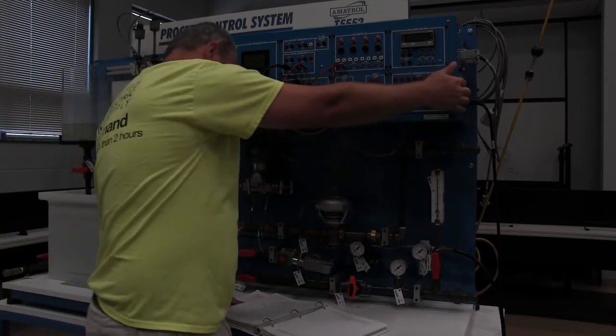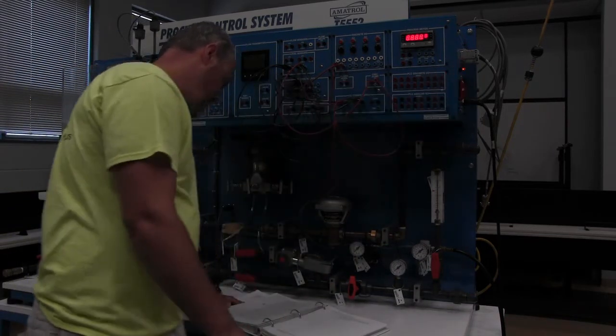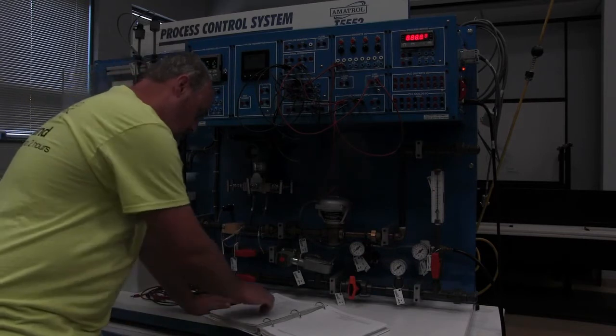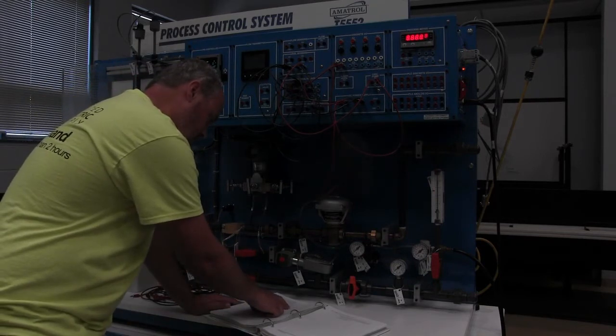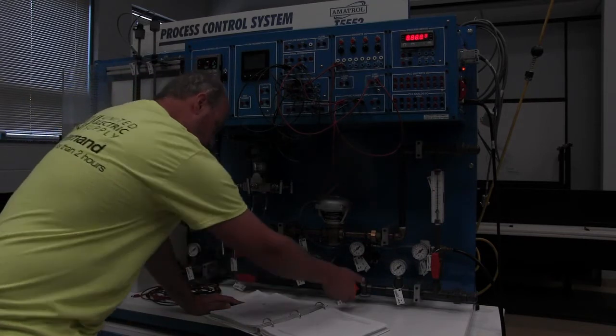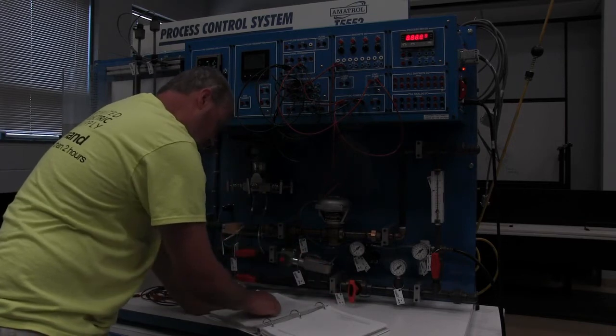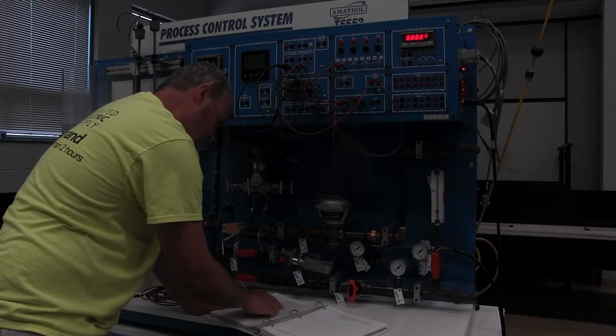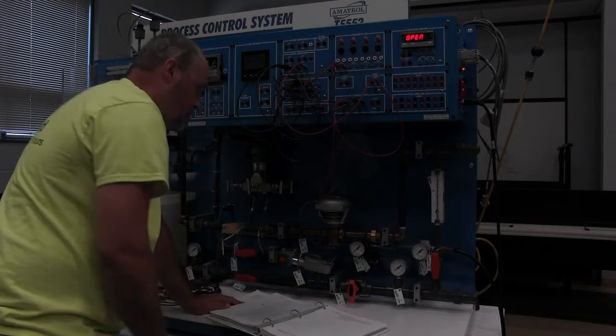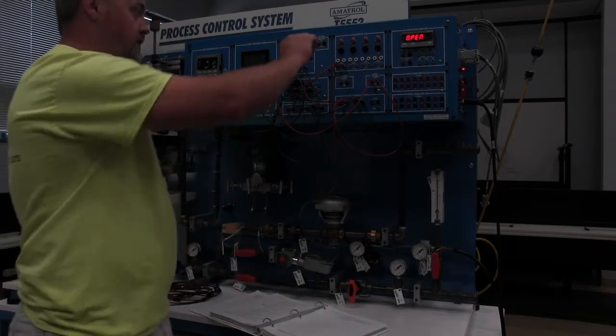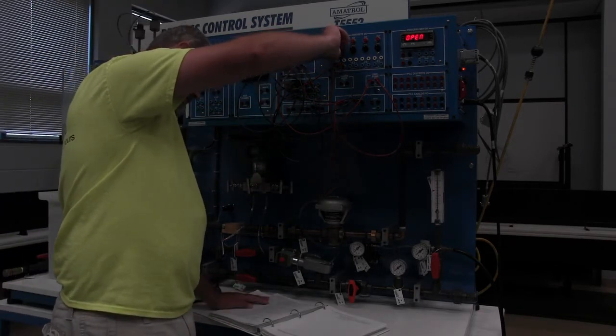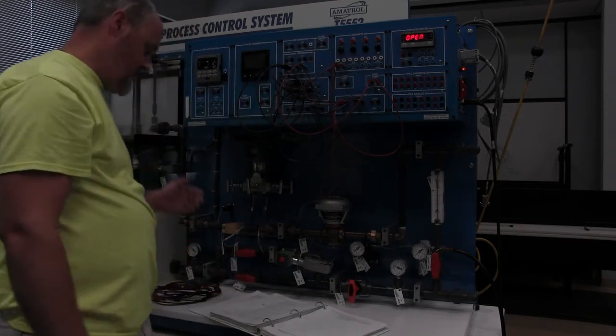So then we're going to power this up. We're going to perform the following sub-steps. Open fully counterclockwise the manual flow control valve FV100. Make sure selector switch 1 is in the off position. Turn the main circuit breaker on. So now it's on, nothing's happening. We're going to go ahead and turn on selector switch 1. When we do, the process tank should begin to fill.